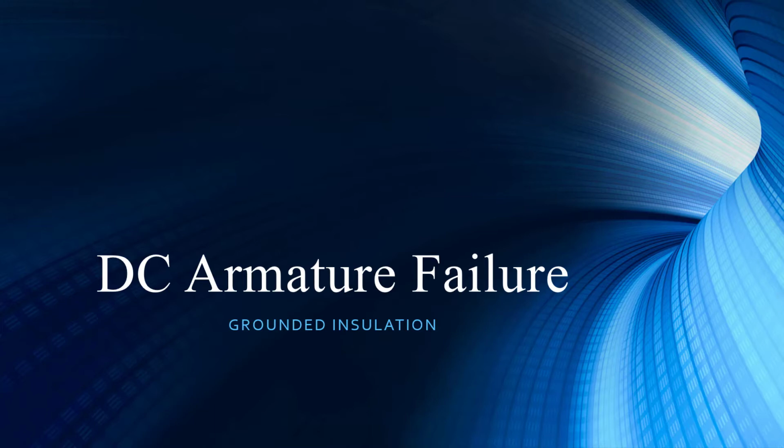And Noah, our customers have come through for us again with a DC armature failure, grounded insulation. Well, we've gone through this quite a bit, but there's some really interesting things about this case study that I think you would find interesting as well. Yeah, I always like looking at DC armatures. I've always said they're the best motors to troubleshoot because you actually can send signals onto the armature and to the field separately. So I always like the DC troubleshooting.